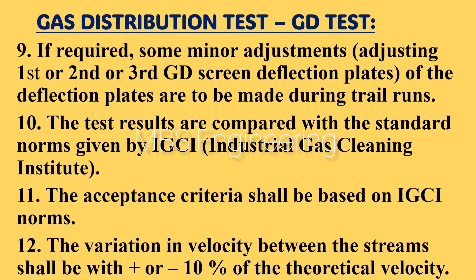Point 9: if required, minor adjustments to the first, second, or third GD screen deflection plates are to be made during trial runs. Point 10: the test results are compared with the standard norms given by IGCI (Industrial Gas Cleaning Institute). Point 11: the acceptance criteria shall be based on IGCI norms. Point 12: the variation in velocity between the streams shall be within plus or minus 10% of the theoretical velocity.